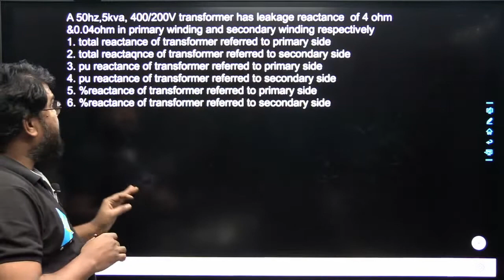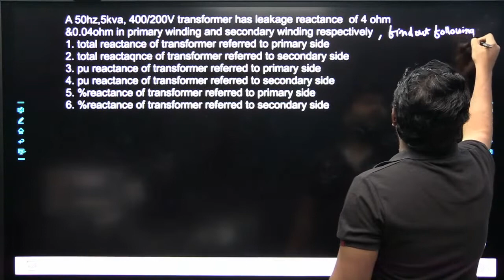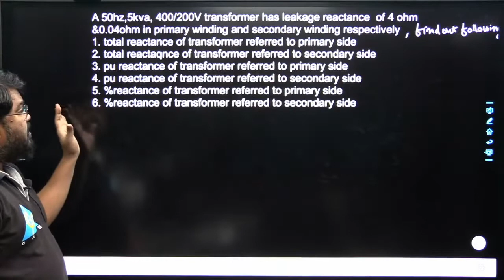Leakage flux occurs in both windings, definitely in primary and secondary, but does not link both windings. That is the difference. Shrutika mentioned that, so the sentence should be: the leakage flux occurs in both windings, primary and secondary. Yes, that's correct. The leakage flux occurs in the primary winding and secondary winding, but does not link both windings.